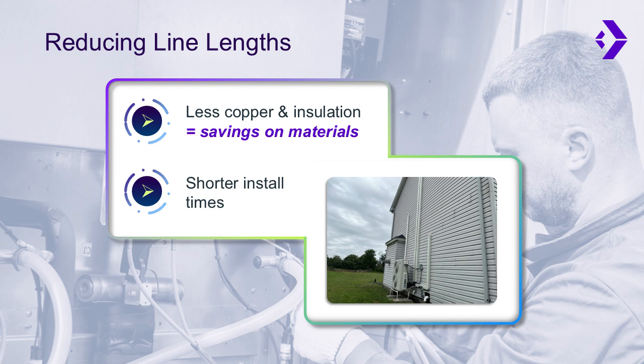It's important to remember that the home's framing can sometimes present challenges when running lines, which may increase the amount of material needed. Taking the time to map out the home and its framing in advance is critical. By identifying the ideal spots for your unit early on, you could minimize the amount of copper, line hide, refrigerant, and insulation required for the line set. In many cases, shorter line lengths not only save on materials, but also reduce installation time, making the process quicker and more efficient. This simple step can have a big impact on both the cost and the overall efficiency of the installation.